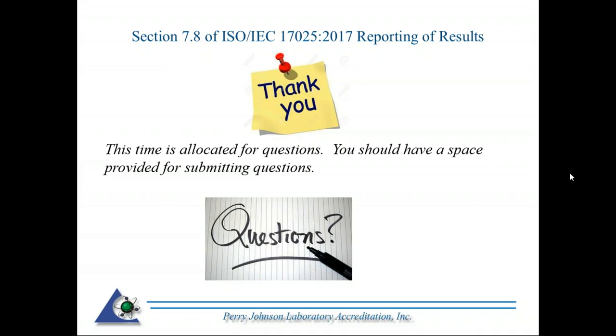In other words, if you're saying something passes, fails, is in tolerance, or out of tolerance, and you made a determination, and I think I gave the example of an ASTM E617 Class 1, which is an analytical type test weight. Let's say 5 grams. If you made a determination that your device is within that tolerance, as long as you're assured it's within that tolerance, you can just use it as nominal. Say 5 grams dead on.